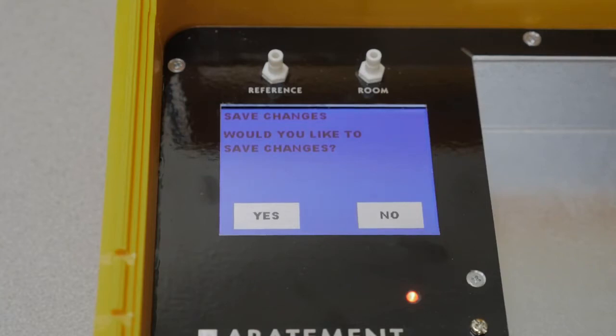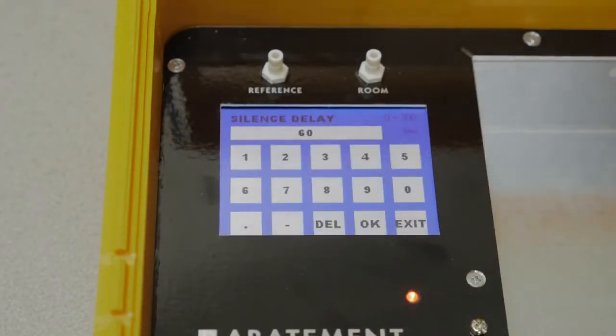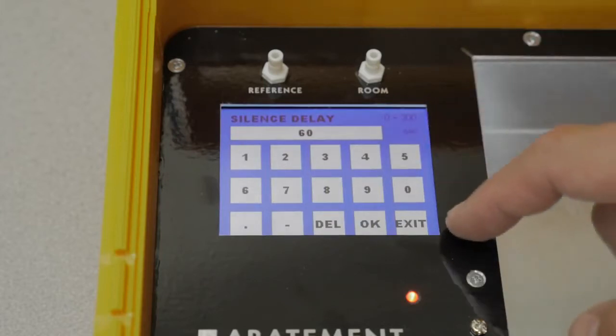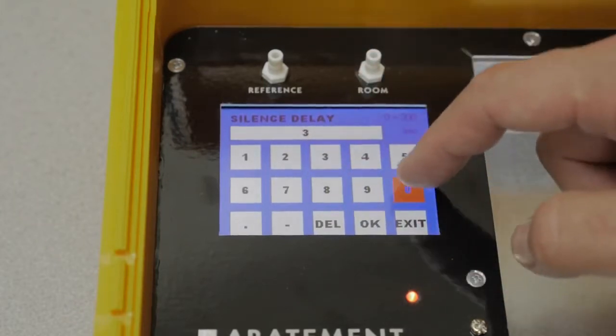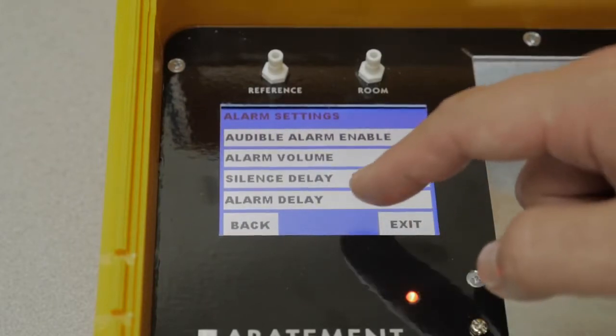As always, be sure and save your changes. Through silence delay, when the silence button is pressed, the alarm will be muted for the duration set. The range is from 0 up to 300 seconds. Alarm delay will work the same way.